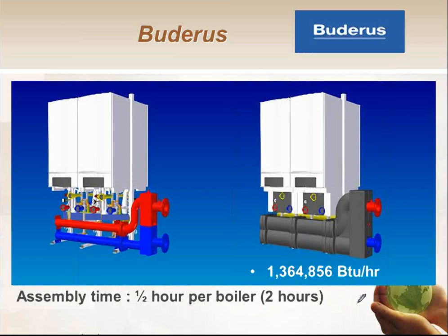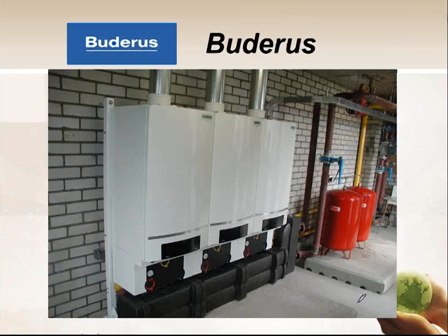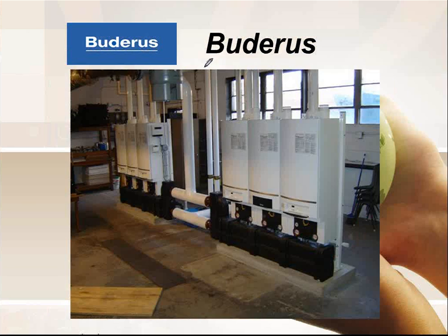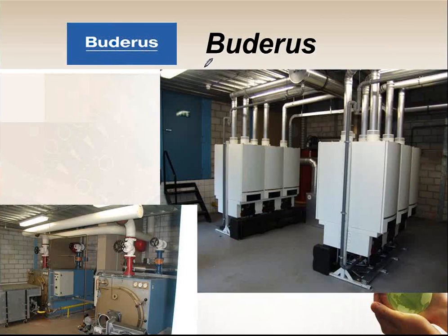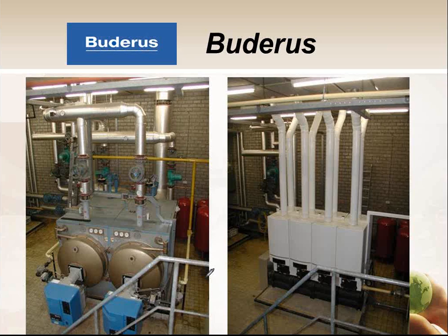We got a whole video on how you set it up, but they manifold together pretty nicely. If you don't want to do back-to-back and you want to put them on the wall, there's kits for doing that way as well. Some of these pictures are showing it with the stainless steel venting, but nowadays on the newer ones we use PVC venting, like that example there, right? So there's 3 of them with a manifolded kit, another 3 manifolded kit, all with PVC venting on them. There's even more. So there's 3 with 3 behind them. So there's 12 of them banked together, taking up less floor space than the old plant that used to be there. There's another example, same kind of thing. There's 8 of them banked together, taking up less floor space.